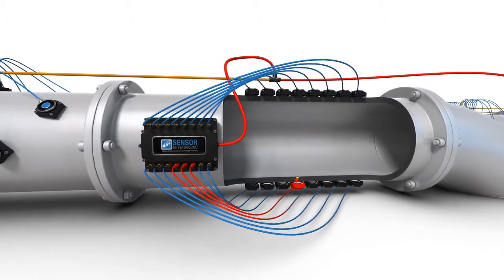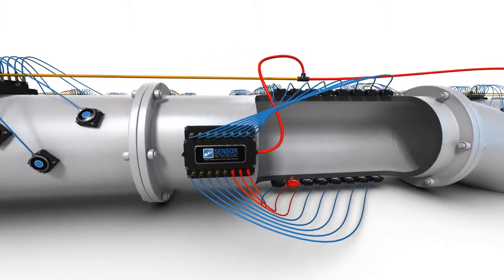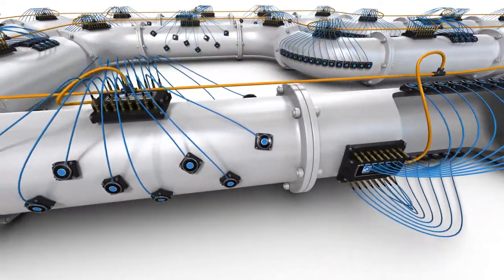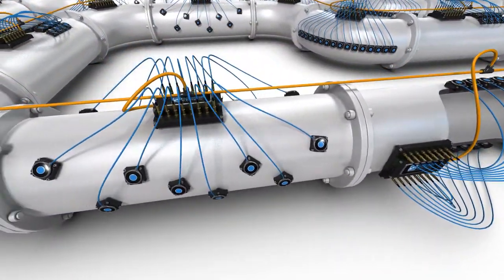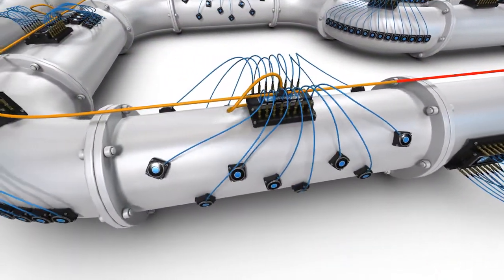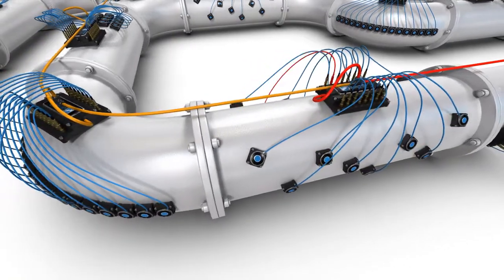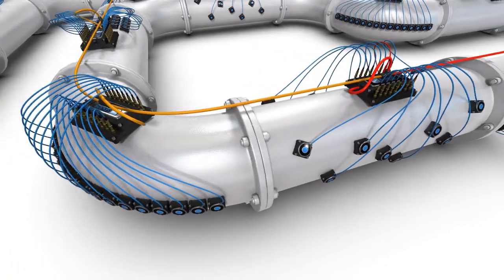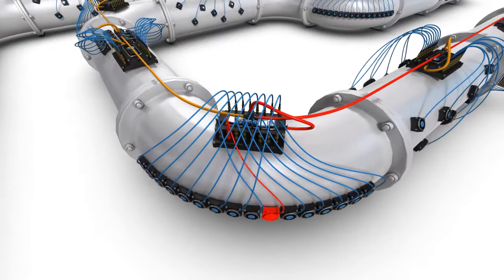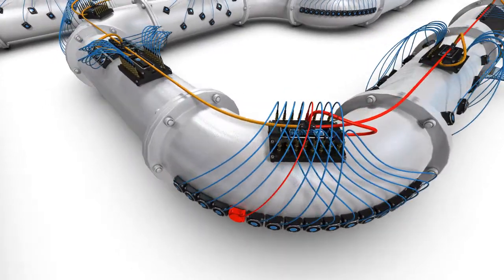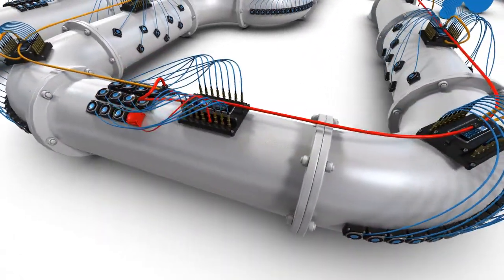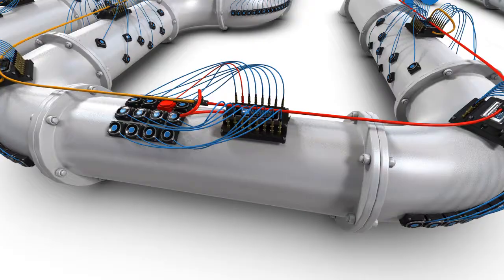The sequence is repeated for the other transducers connected to the DSI. Once a DSI has successfully communicated measurements from all its transducers, the next DSI is prompted to do the same. For any given DSI, transducers may be arranged randomly, or in a linear or area array, giving you the versatility to monitor unique geometries, such as pipe elbows.